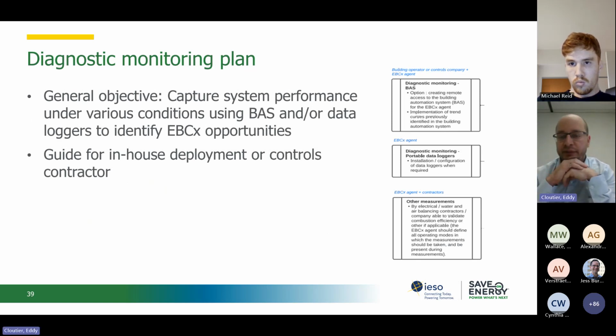Diagnostic monitoring involves collecting detailed operating data on the different systems in a building. For example, collecting data on the position of the economizer damper during a day, data on the mixing temperature in the air handling unit, data on the humidity and temperature in the supply and return of a system, and so on. There are as many examples as there are kinds or types of buildings and systems.